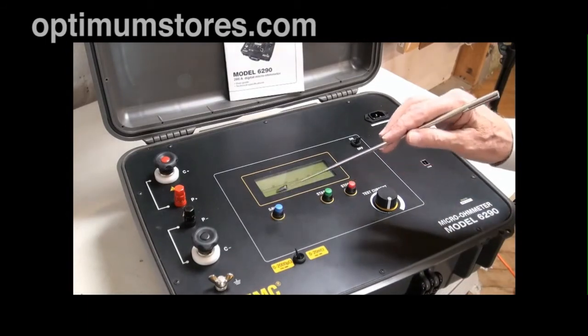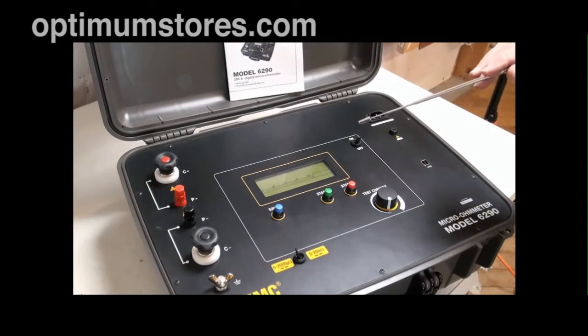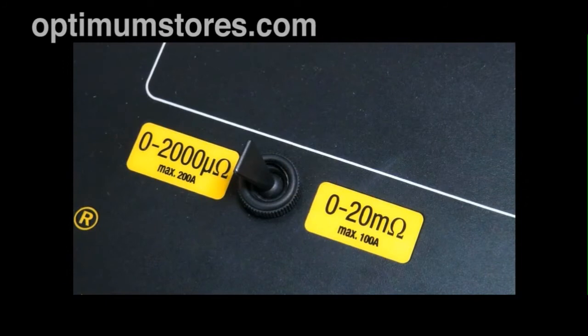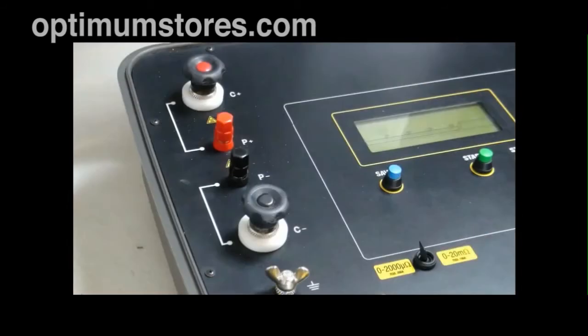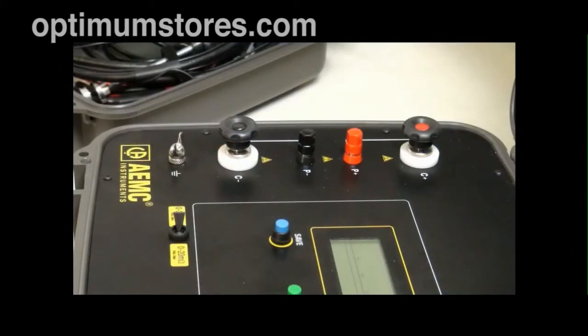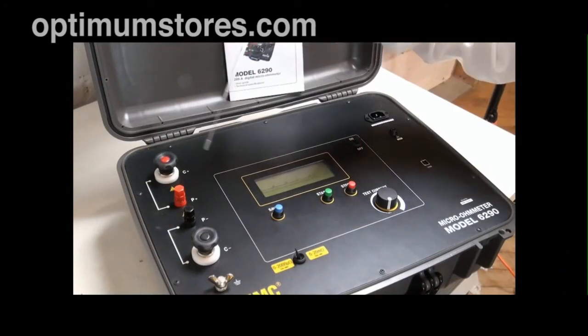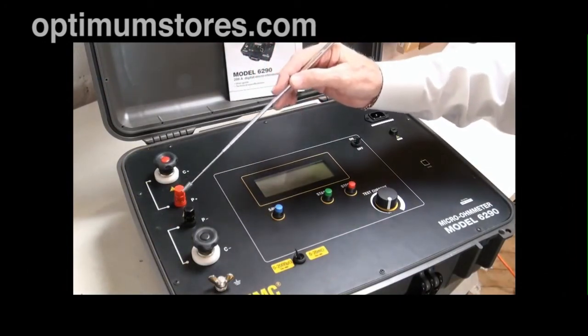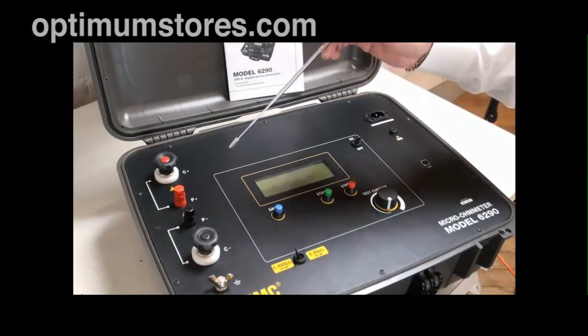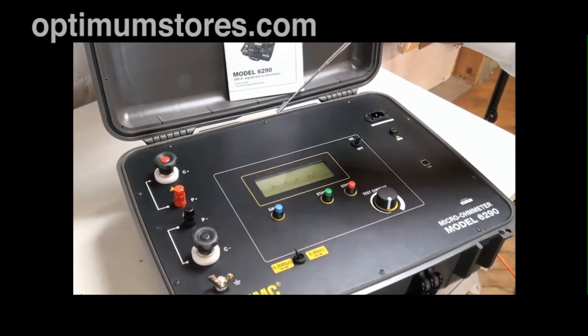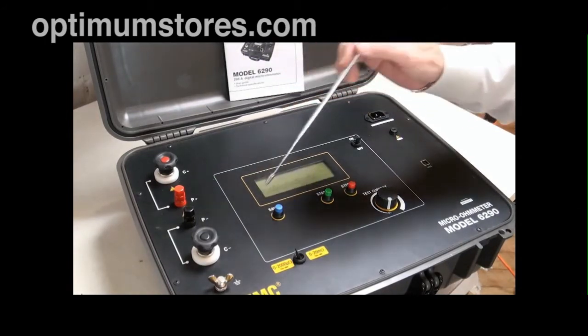We start a test and we stop a test, and to put it in memory we hit the save button before we stop the test. And we do have a selection right up front. Do we want to go with 100 amps or 200 amps? We have that selector switch, and that'll allow us to read higher end readings of 20 milliohms versus 2 milliohms. Our input lugs, these are our injection lugs, which we send the current through the test specimen or test device, back and return path, and then the Kelvin clips, which give us unprecedented accuracy, eliminating the resistance in our test cables because we are measuring right at the point of contact.